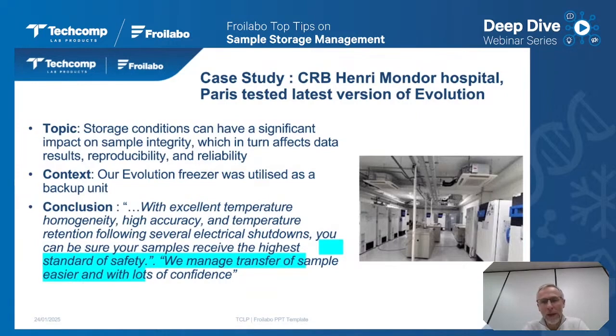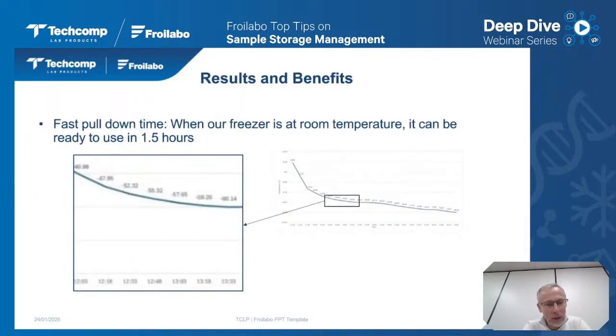And the main conclusion of this test is that they managed the transfer of samples more easily and with a lot more confidence than before. Why? Because the first thing is, when they need to start this unit to get to -80 degrees, they observed a fast cool-down time. And it's very important because when you have a yearly maintenance, you can easily plan to turn on the backup unit as you want, several hours before the transfer.